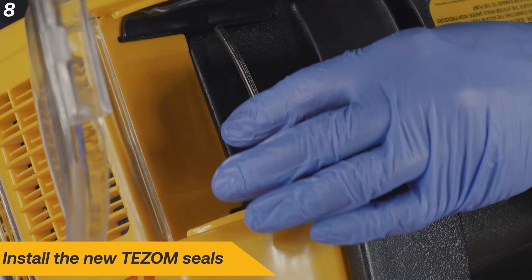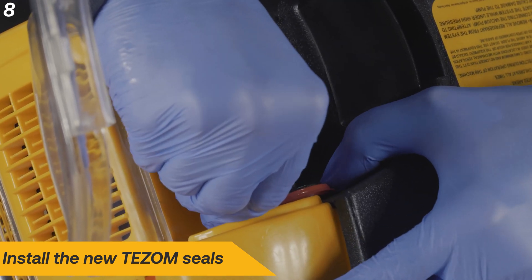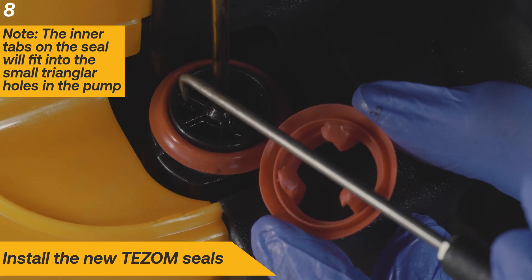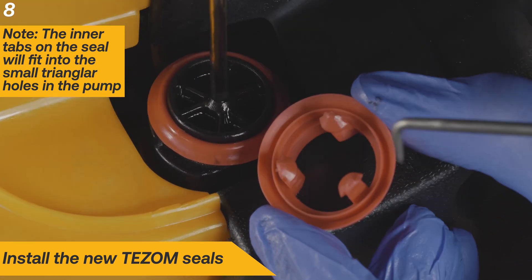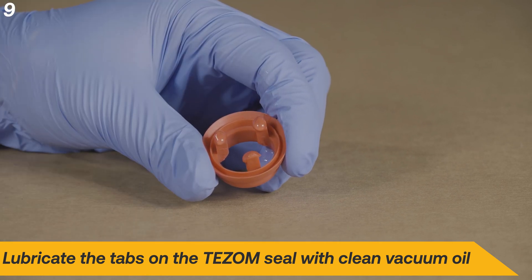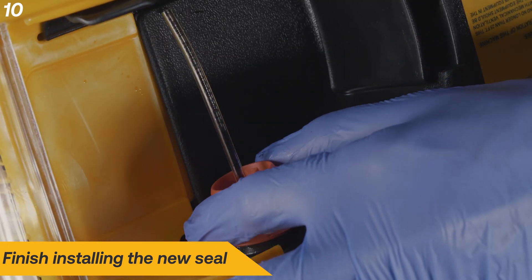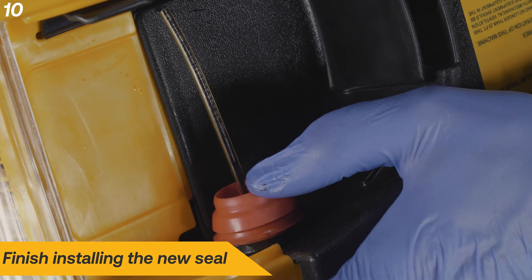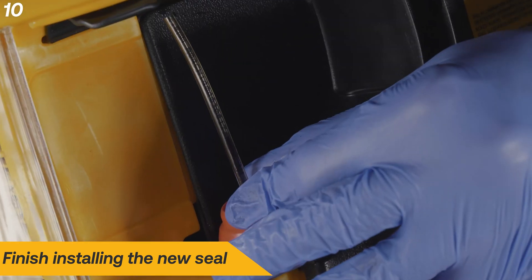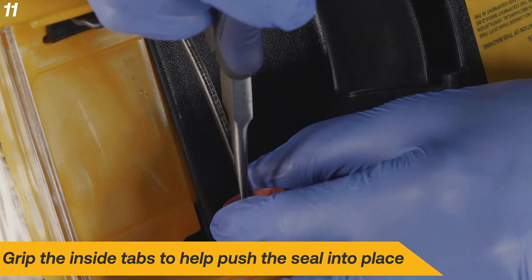Install new TEZOM seals, starting with the smaller upper seal. Orient the tabs on the lower seal with the triangle shaped holes on the pump. Lubricate the tabs with clean vacuum pump oil for easy installation. Finish installing the new seals. You can use needle nose pliers to assist with installation if the seal won't seat by hand.